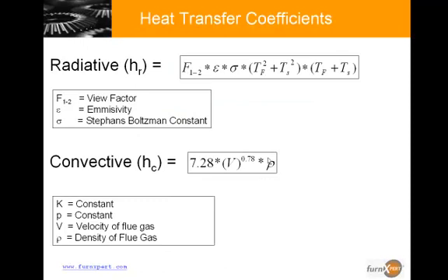Radiation heat transfer coefficient is given by the top equation. The radiation heat transfer is dependent upon view factor which is F12, that is a fraction of the area of the charge seen by the hot walls, emissivity given by epsilon usually the value is from 0.8 to 0.95 for steel, Stefan-Boltzmann's constant sigma, and the furnace temperature and the steel temperature.